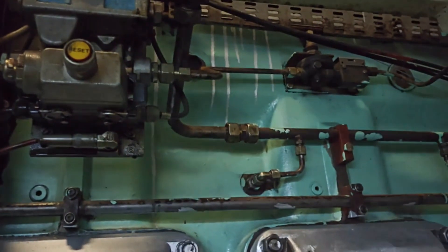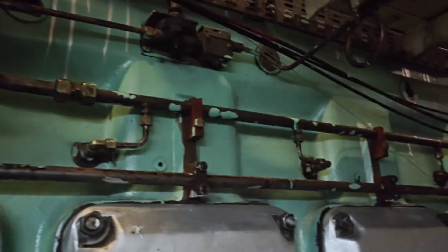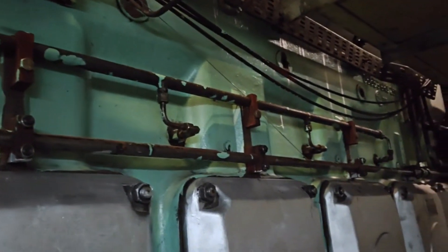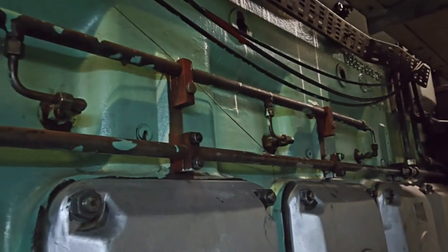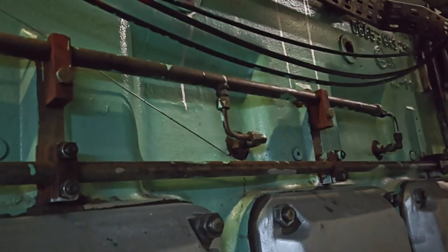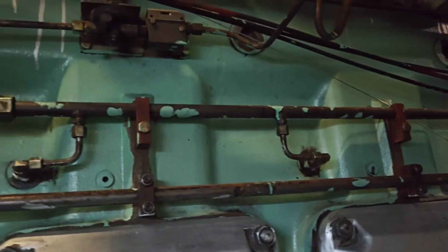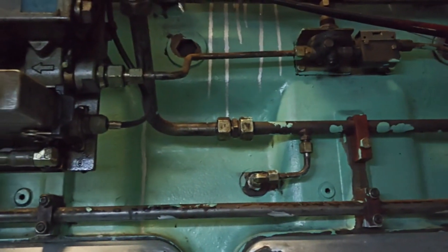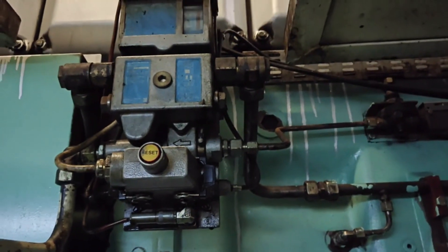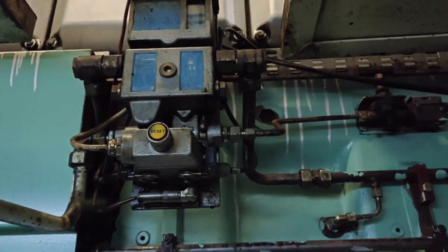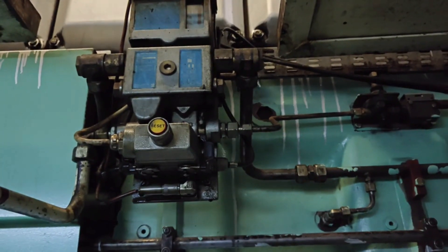This type of OMD is called Obscuration type OMD. It uses a light beam to detect interruptions from oil mist particles. But this type of OMD has disadvantages like non-linear response and inability to measure multiple points.